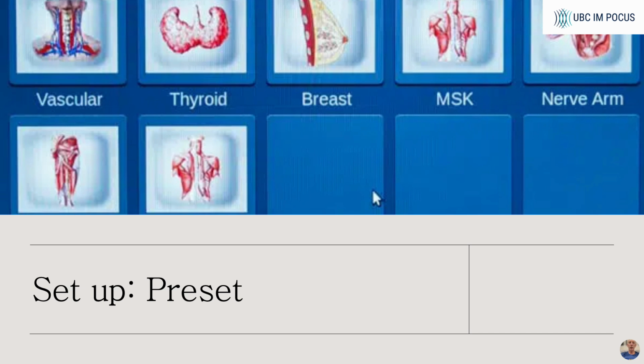In this image, a vascular preset is provided. Vascular scanning frequently utilizes Doppler functions, and therefore vascular presets will include access to Doppler. You will still need to consider whether the specific Doppler setup is appropriate for your needs. In particular, adjustments may be required depending on the velocity of flow that you are looking at.